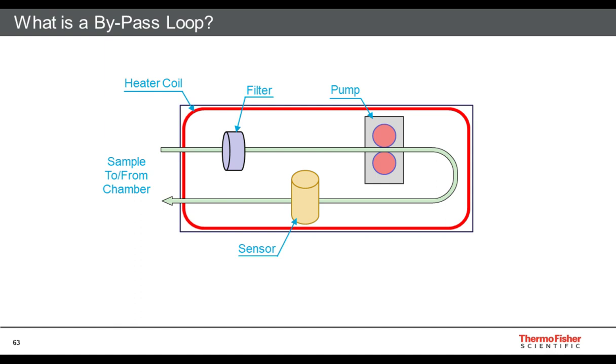Now, because this is outside the incubator chamber, we also have to have a separate heater. So this compartment is also heated to the same temperature as the incubator chamber, 37 degrees, but it's a completely separate heater. And it's not something that you're going to calibrate if you check the temperature on your incubator. You just don't have access to that. My point here is that a bypass sensor simply does not react to the same conditions that your cells are in the incubator chamber. It just can't.